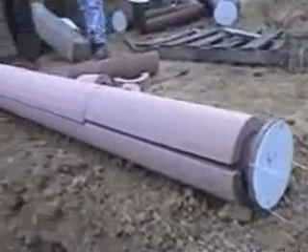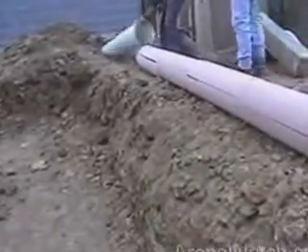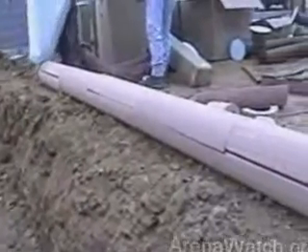The piping, which has been factory pressure checked, they're beginning to pre-insulate it, and they want to insulate it actually outside the trench first. We're using a 2-inch urethane type insulation, which is a closed cell foam. Won't be impregnated by moisture in any fashion.